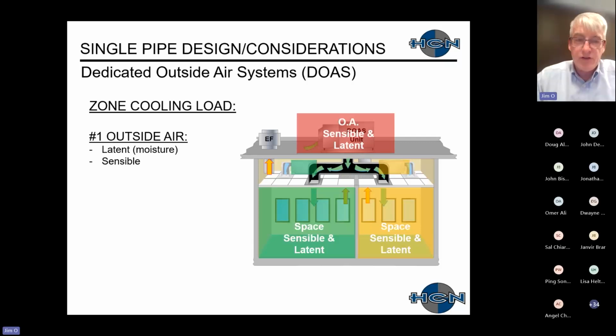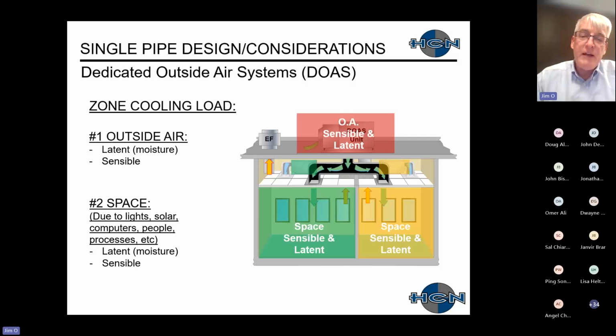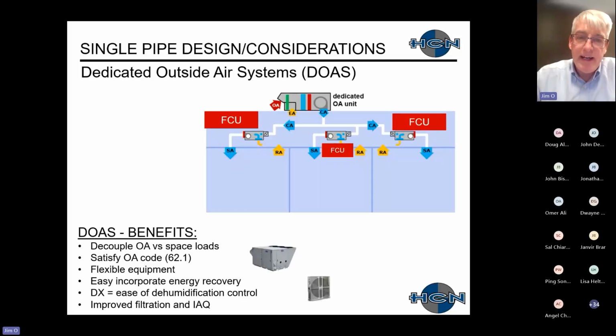Here's a quick slide just showing a dedicated outside air unit on the roof. Your zone cooling load is traditionally made up of two major components. Your outside air is typically handled by the DOAS unit in this case. The outside air has the majority of your latent moisture as well as sensible. And then your space cooling load, which is often due to lights and solar, et cetera, is mostly sensible with just a little bit of latent cooling in that. So with dedicated outside air systems, the benefit is that you can decouple your outside air and your latent space requirements versus what's in your space.